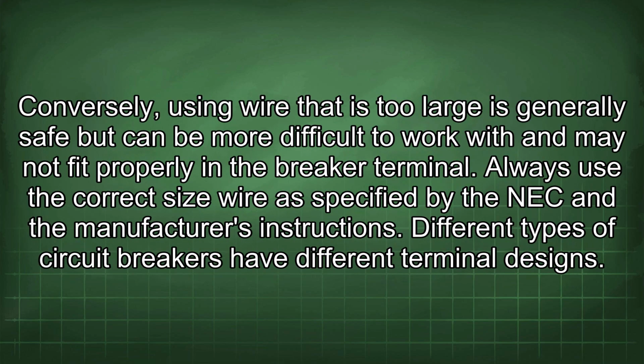Conversely, using wire that is too large is generally safe but can be more difficult to work with and may not fit properly in the breaker terminal. Always use the correct size wire as specified by the NEC and the manufacturer's instructions.